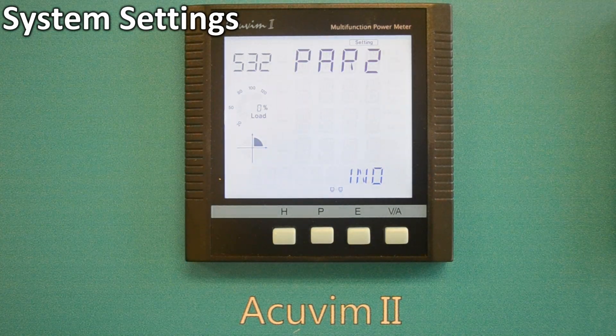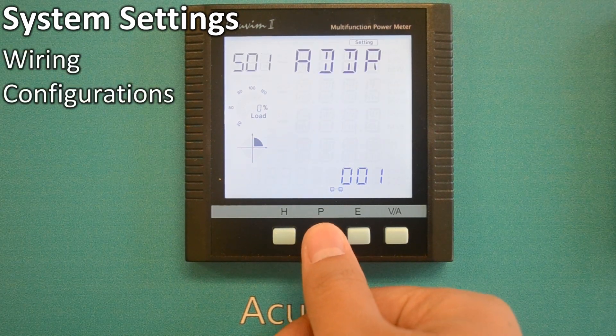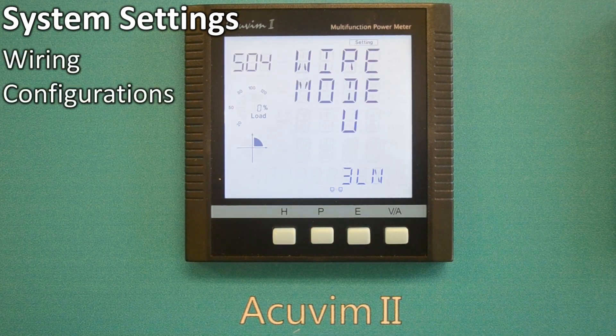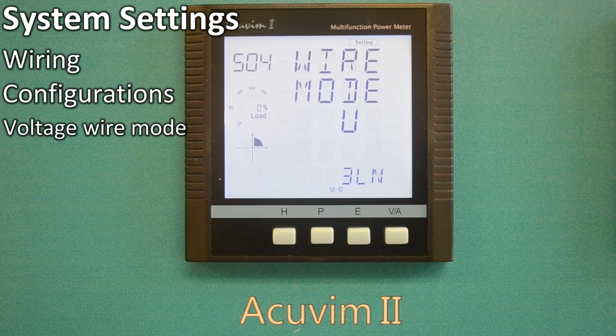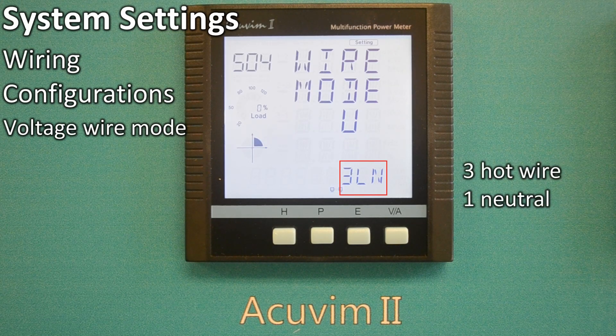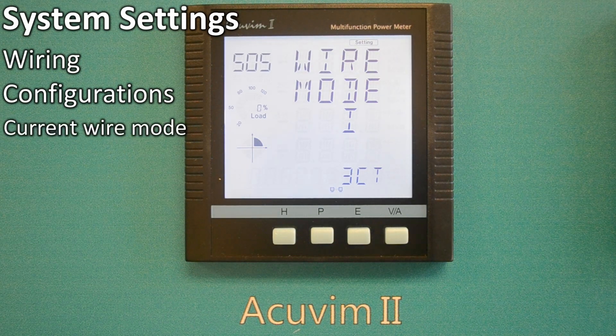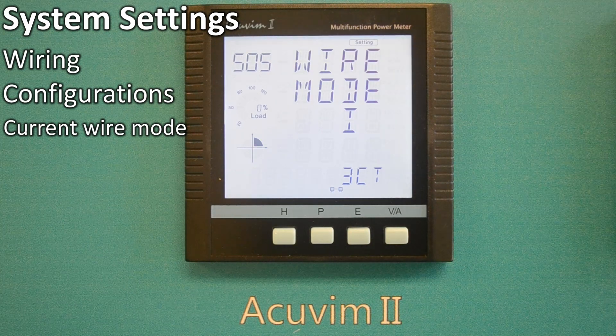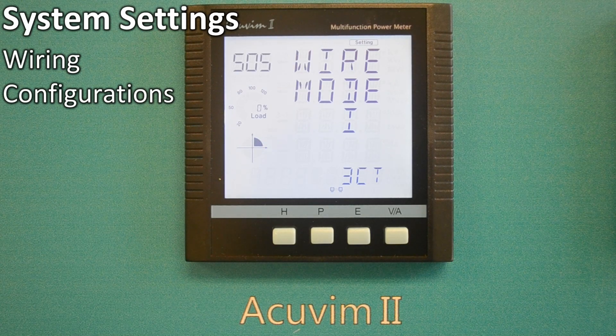Next, we look at wiring configurations and PT and CT settings. Pressing P a few times will take us back to the fourth screen, wire mode U3LN. This means the voltage wire mode is three hot wires and one neutral. The next screen indicates wire mode I3CT, meaning the current wire mode is 3CT. 3-line, 3CT wiring is popularly used in low voltage systems.